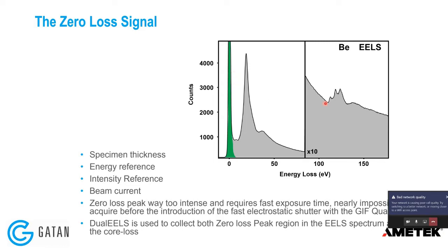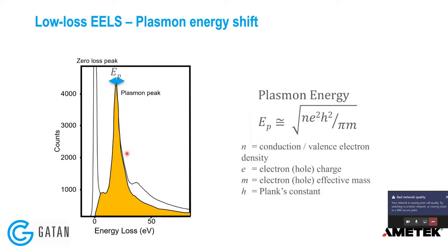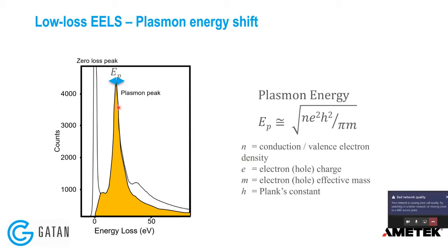The plasmon peak is the second most important feature in the EELS spectrum, originating from electrons that excite electrons in the valence band and polarize them. The intensity of this peak is proportional to the electron density of your material. Small changes to the material's electronic structure produce changes in the plasmon peak, and from this you can extract the electron density. This is all enabled by the Gatan software and runs automatically, enabling a kind of chemical phase mapping.